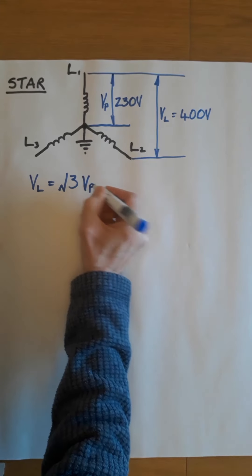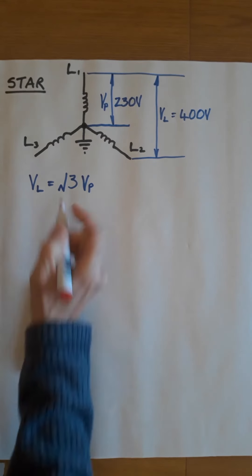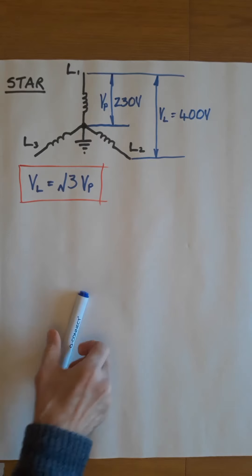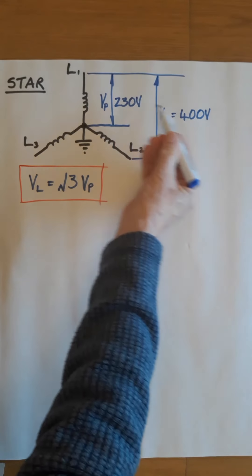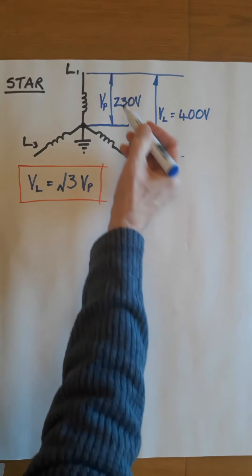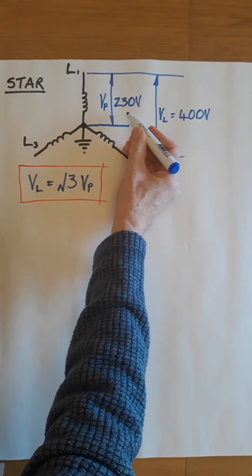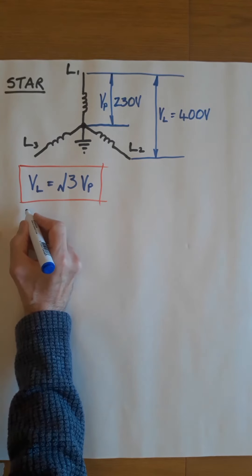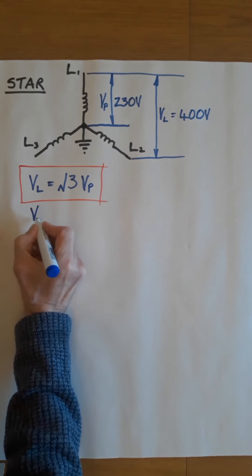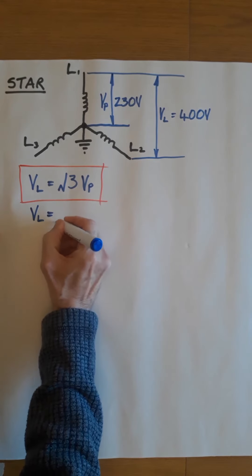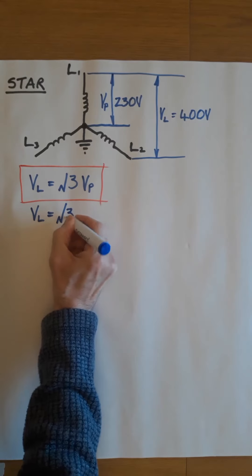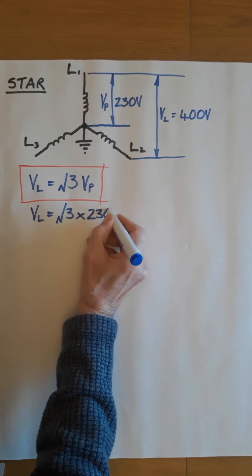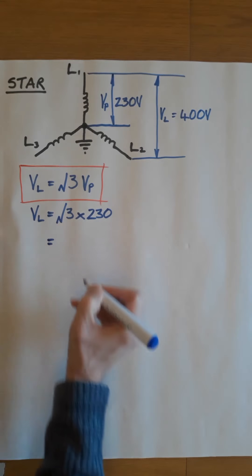This is a formula to remember; this is important. So if we were to just use these numbers, if I know that our phase voltage is 230, I should be able to calculate the line voltage. So let's do that now. VL equals root 3 times 230. If you put that in your calculator and work it out...